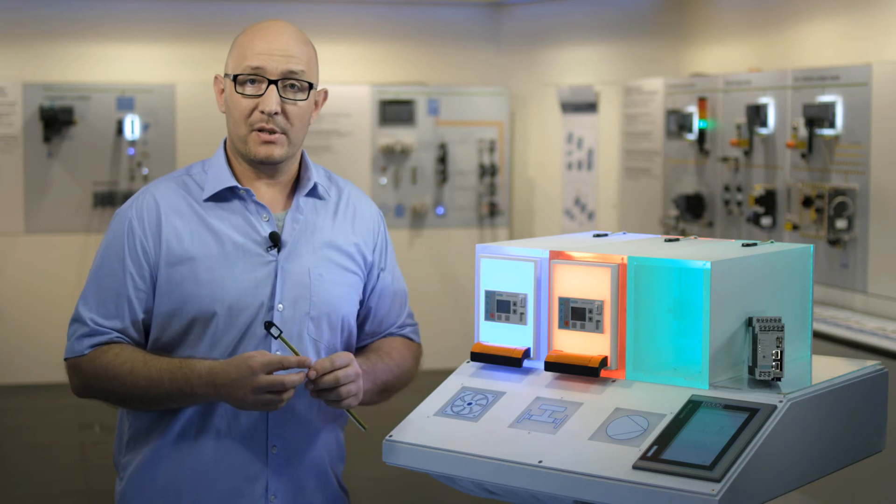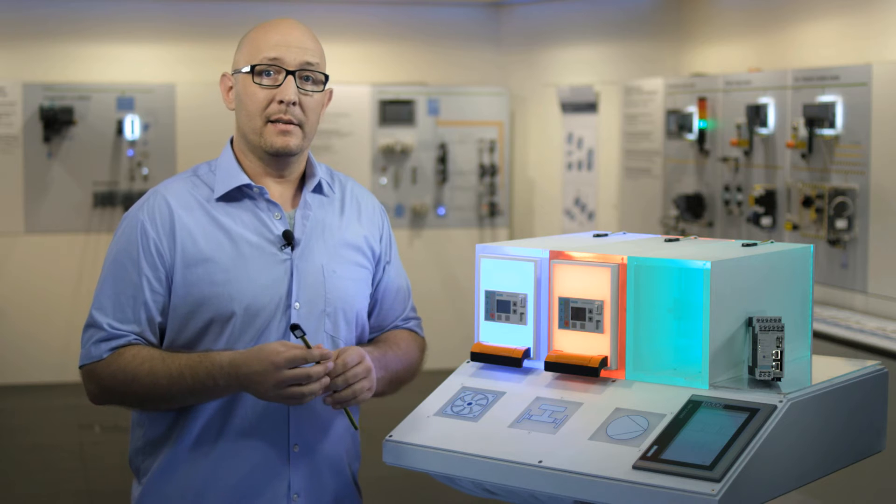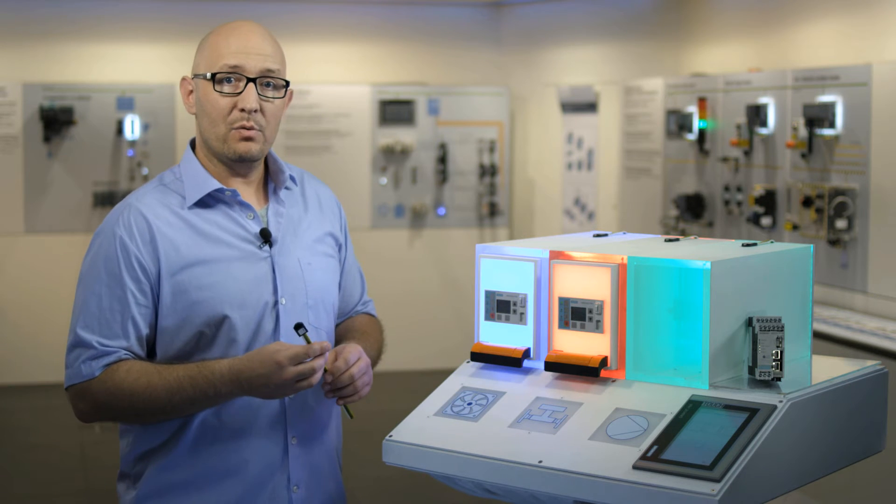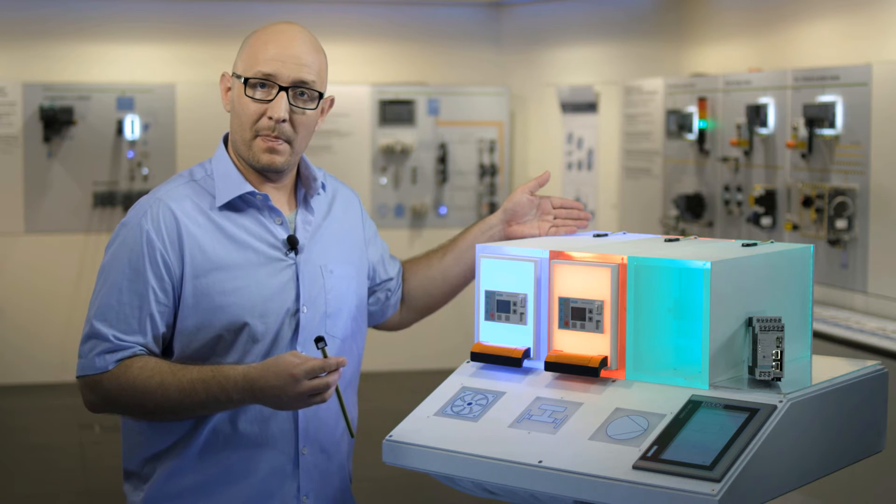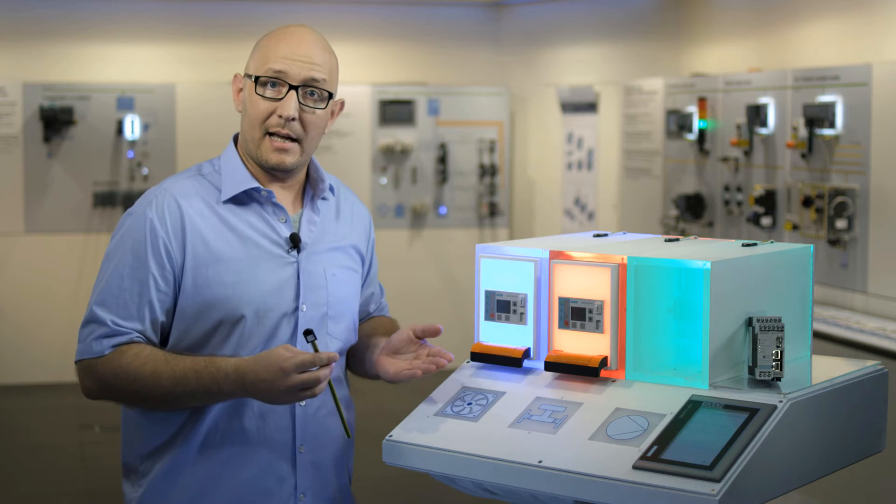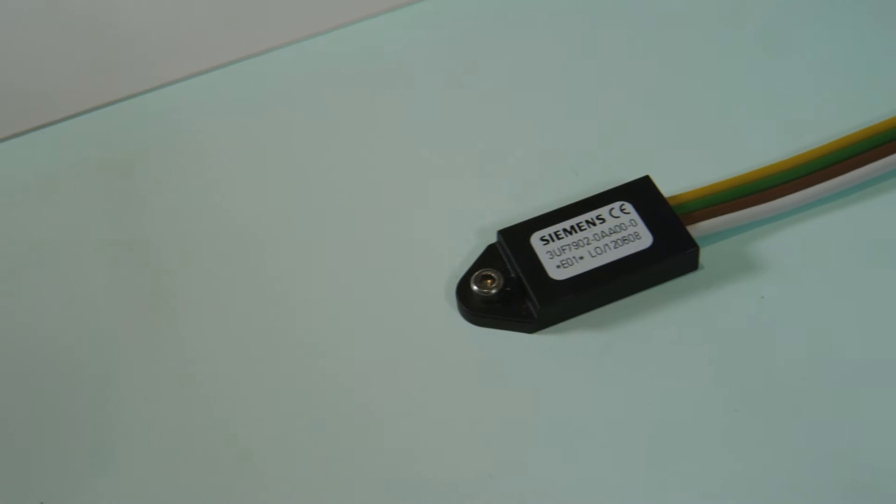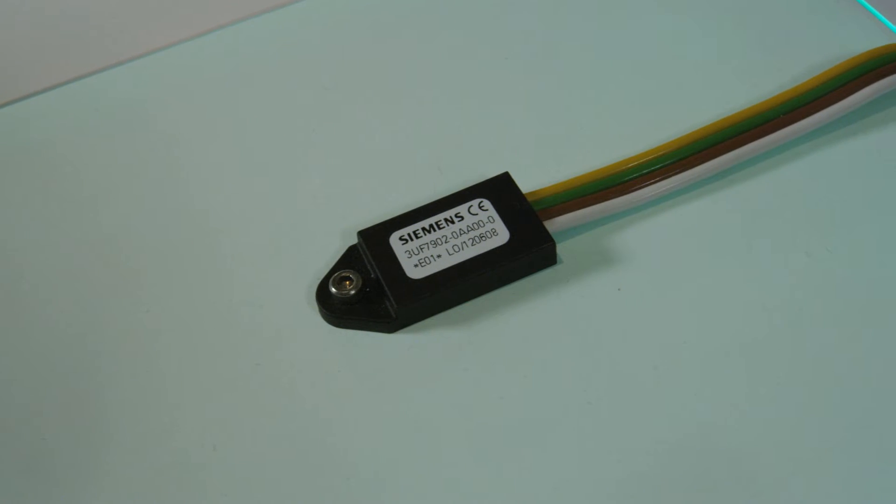All parameters and address data of the motor feeder are not only saved in the device, but in this Initialization Module as well. Because the Initialization Module is permanently installed in the switchgear, it is not replaced when withdrawable units are replaced and therefore cannot be confused.